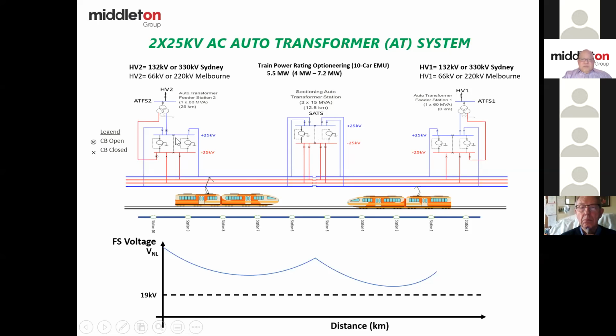But of course, if the system is designed properly, you'll find that you should be able to feed from one end to the other. This is 25 kilometers long, and that will have the benefit of being able to utilize all your regenerative braking from the trains, so that regenerative braking energy can flow freely between the two sides of the system, past the neutral section. And this is just one way of creating a neutral section. There are other ways which I've come up with: using rigid overhead conductor bar, you can actually create a switchable neutral section. You keep all the switches closed for current flow through, and when you need to, you just open the switches, then you're back to feeding from both ends. So that will be an improvement.